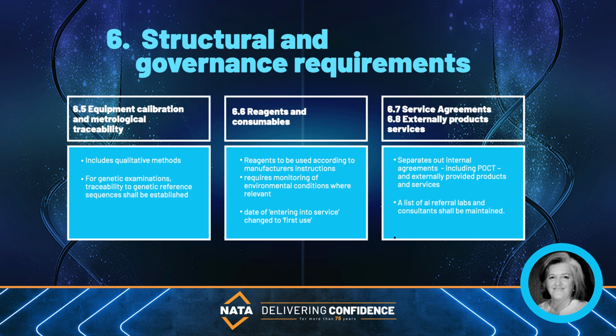Under Section 6.6, labs shall have a process for the selection, procurement, reception, storage, acceptance testing, and inventory management of reagents and consumables. They shall be stored according to manufacturer's specifications and conditions monitored where relevant. This includes goods that are received and stored off-site. Each reagent or new formulation of reagent, new lots or shipments shall be verified before placing into use or before results are released. Patient samples are preferred when comparing different reagent lots to avoid issues with commutability associated with QC materials.